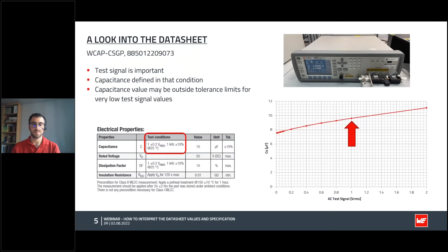So here I plot the capacitance measurement versus the test signal at the capacitor. As you can see, the value is fine at 1 volt RMS. But if I had only set 1 millivolt RMS, as is very common as a default setting in some equipment, I would be outside of the tolerance limits of the capacitance. So maybe I can imagine I will be calling my capacitor provider and complaining about quality issues.